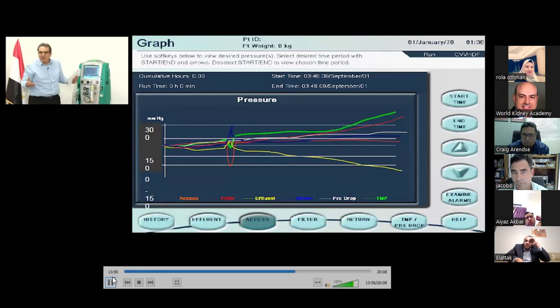Of course, here, because it's a simulation, there is saline, there is no human blood. I'm unable to see transmembrane pressures, access and return pressures, as what you would see in a normal clinic. So looking at the history of the pressures using the pressure history menu, you will be able to diagnose that this is a pressure accumulation problem.